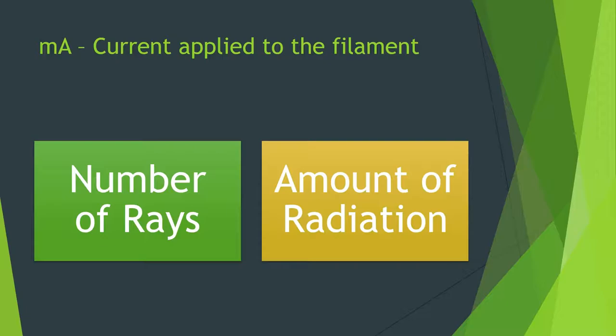Kilovoltage affects how energetic the X-ray beam will be for that split second. The current is the electrical charge applied to a coil of wire inside the tube, and they use something to focus it to give fine and broad focus. So increasing the current increases the number of rays. We need to think about how thick and how dense the body part is — can we give 150 kV and 1 mAs for everyone? No, because there just aren't enough rays to adequately penetrate the image.